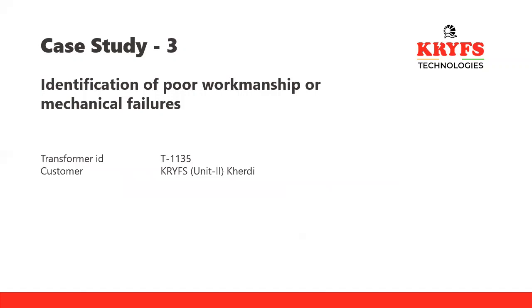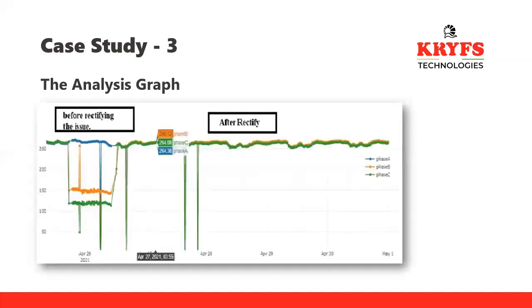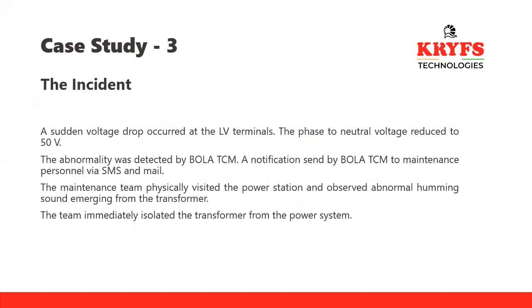The third case study, which we found in our own factory, since we tested this device 3 years back in our own factory. With this graphical dashboard representation, you can see there was a voltage variation on a particular phase, and the indications went to our maintenance team. In this incident, there was a sudden voltage drop on the LV terminal. The neutral voltage reduced to 50 volts, the abnormality was detected by our transformer monitoring device, and the alerts went to our maintenance persons via SMS and email.